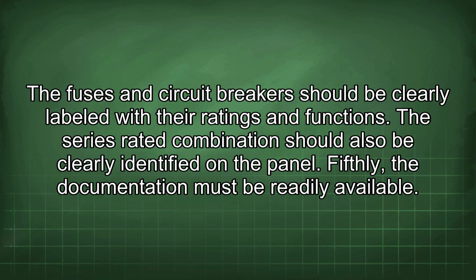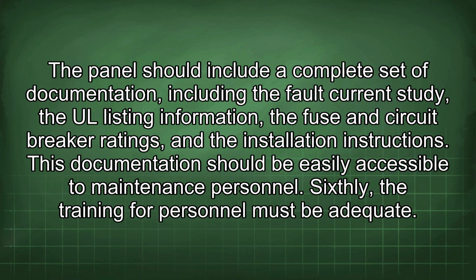Fifthly, the documentation must be readily available. The panel should include a complete set of documentation, including the fault current study, the UL listing information, the fuse and circuit breaker ratings, and the installation instructions. This documentation should be easily accessible to maintenance personnel.